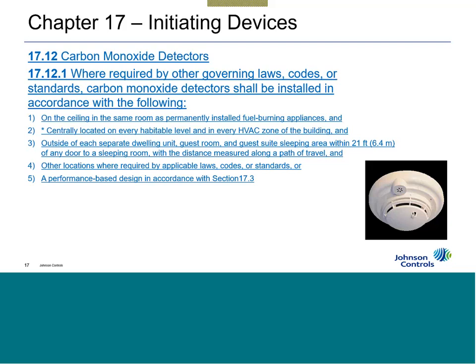And then in addition to that, a lot of our problems have occurred where people are sleeping. Carbon monoxide affects our body by making us feel nauseous, sick, like I've got the flu, I want to lay down, I want to take a rest. So naturally, we want to make sure that the areas where people are supposed to be sleeping are also protected. So what the code has added is, let's make sure that there's a CO device outside of each sleeping area, each door within 21 feet. So if it's a guest room, guest suite, college dormitory, apartment complex, hotel, we want to have these CO devices down the hallway within 21 feet of every door.